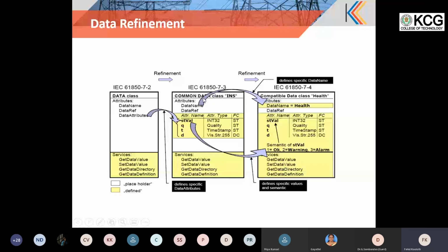Then 7-4 further refines it with the logical nodes and their data elements. Like actual health is under the logical node, health is the data name, and under that ST value, so health status, and in that all the services are defined. So it is a very standard, providing further refinement of data, and once it reaches 7-4, this is complete on the logical side.